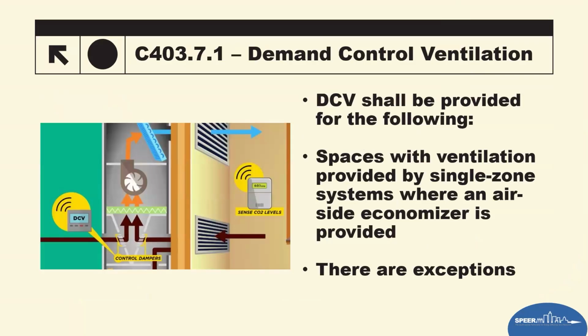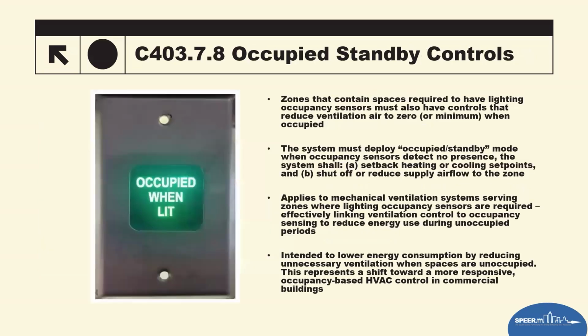There is now also demand control ventilation. This section introduces DCVs that must be installed. These are smart ventilation strategies that adjust outside air based on actual occupancy, sometimes based on a CO2 sensor, to avoid overventilating when the ventilation isn't needed. Under the 2024 code, it's required for certain spaces served by a single system when an air-side economizer is included. The idea is to avoid bringing in and conditioning unnecessary outside air when only a few people are present. There are exceptions for that, such as spaces where ventilation loads are minimal and where other control methods are already being used. Overall, DCV is about balancing comfort, indoor air quality, and energy efficiency, ventilating when the space fills up and then scaling back when the space is empty.